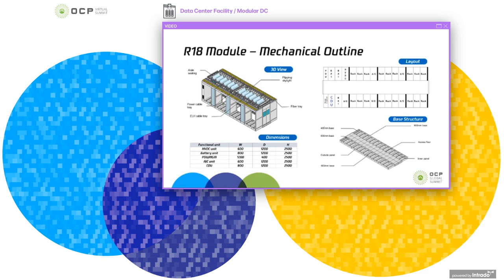Here is a typical configuration of R18 modules. It contains 18 racks, that's why R18 comes from. It is equipped with UPS, battery, air conditioning, CDU. All those standard components could be shipped to the room via the building elevator and are easy for on-site assembly. The height of the base structure is 40 cm, used for deployment of the pipelines. The battery unit and the CDU are 800 mm wide, and all other components are a standard 600 mm width.